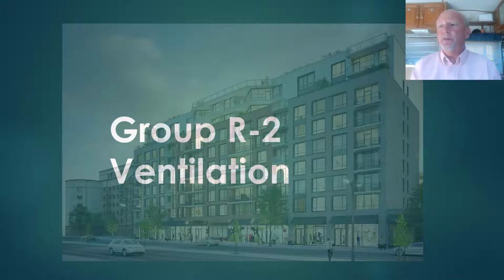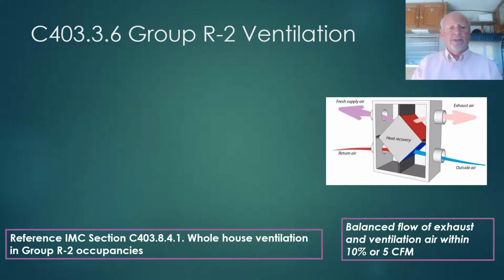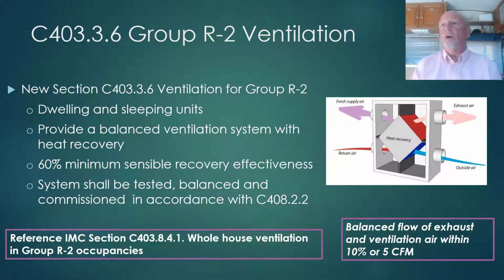So let's talk ventilation, and specifically Group R2 buildings. This is a significant change in the code for Group R2 buildings, which is multifamily buildings, and in the commercial code, that's multifamily buildings 4 stories or greater. In the past, ventilation was handled through Chapter 4 of the IMC, and basically you were required to have either a whole house fan system with air inlets or a ducted distribution system through a central station air handler. That has significantly changed for the 2018 code cycle, and it's also changed in the provisions of the IMC for the whole house ventilation.